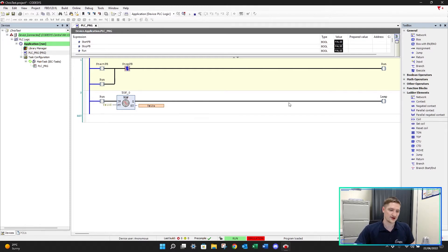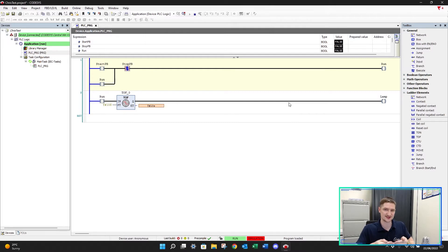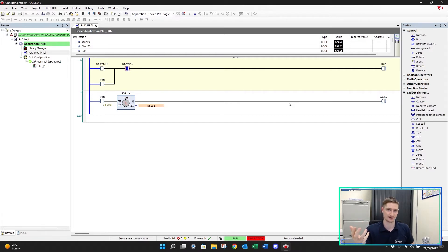The TOF is just like the TOF timer inside the Siemens TIA Portal. When we give it the enable signal, it turns the output on straight away - the timer will not run. It then waits until the signal turns off. When the signal turns off, it continues running that output for a period of time until it's elapsed, and then it will turn off the output.